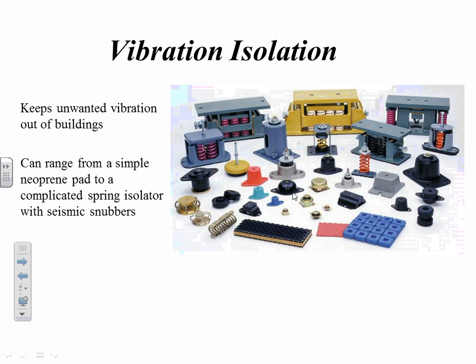Well, that makes sense on engines that are relatively small. On bigger sets, like a 2 meg set that might be, or the big one that I showed you in that picture, that 3250, those are solid. I mean, they weld everything right to that skid, so it's all one piece, if you will. In that case, we go to an isolator like this. It's a spring isolator. And you see some of these have little stuff on the side here. These are adjustment screws for the side of this. This is actually a seismic isolator here. And there's adjustments you can do for those, for seismic areas. So a lot of different kinds.